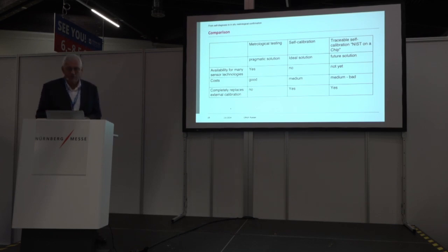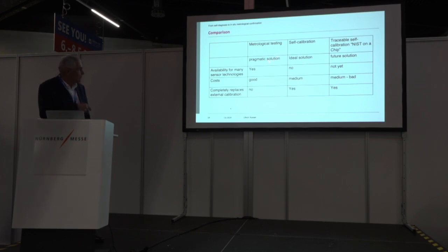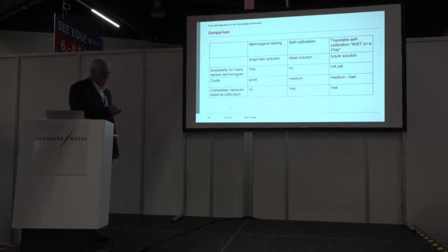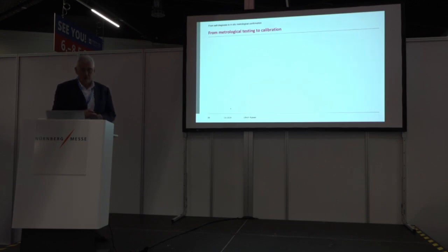And here is just the comparison of the three methods. In general, you have the metrological testing I talk about, the self-calibration, and the future method, which I just name NIST on a chip. This is a future solution. This is an ideal solution, but this ideal solution is not available for all measurement devices, for all measurement methods. This one is available for all measurement methods. The costs are good. It's a few electronics which you put in, for example. Cost here maybe medium. I think medium to bad. But at the time today, you might have that, which is only available for a few measurement types, or this, which may be available for a lot of measurement methods. And now I try to tell you how this will lead to a change in calibration period or calibration time.